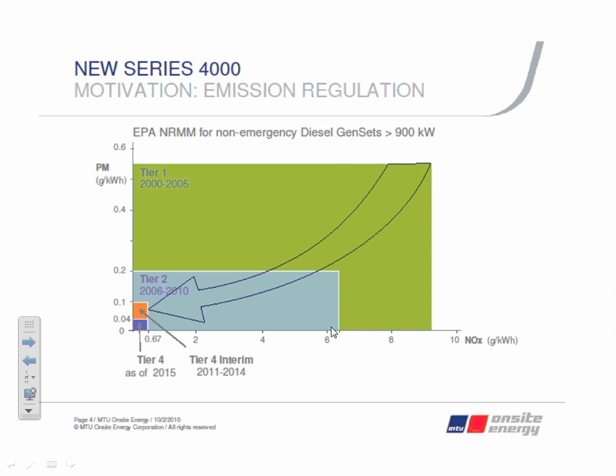Tier 1 is the green box. Okay, and then over time, if you remember my graphic of improved emissions, we moved in 2006 to 2010 to a Tier 2 engine, which is the blue area here. Tier 4 interim reduces down to this box that's orange and the dark blue, and the final in 2015 is down here under 0.67, down from 9 point something grams per kilowatt hour. So this little box is where we're going in 2015. To do that, the total reduction has been very, very expensive. But it's a good graphic to illustrate that point.